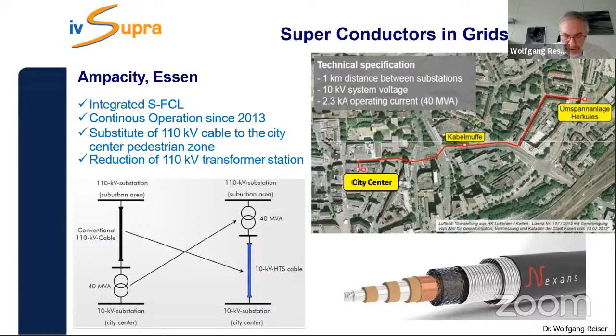Another example is the use in a normal 10 kV cable. This cable has been running since 2013 in Essen. The reason was that in the city center there was a 110 kV transformer station, and over the years the city center developed into a pedestrian zone, making it very difficult if a fault were to occur. So they wanted to remove the 110 kV line from the inner city to a suburban area, and installed a 40 MVA superconducting cable to the city center instead. That was a very good solution, and it has been running since 2013 without any problem. So superconductors are there and they can be used.